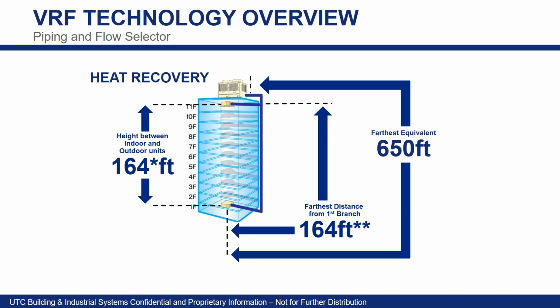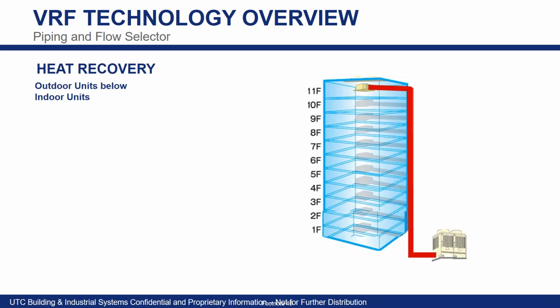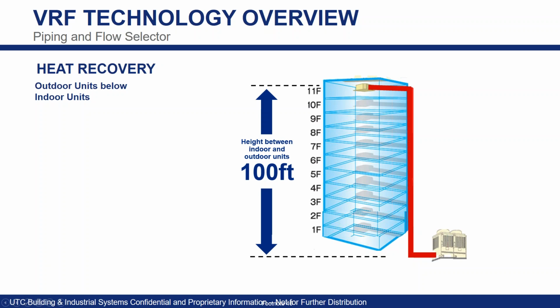Furthest equivalent, so that's total piping length, right? 650 feet. So heat recovery with our condensing units grade mounted, you're going to see 100 feet. So what does this tell you? Ideally, we want our outdoor units to be above our indoor units if we do have some pretty large vertical constraints to tackle or to overcome.